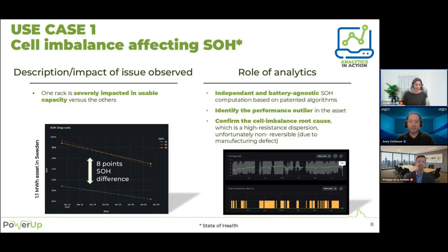What you see on the graph on the left are three lines, each representing one battery rack of the system. As you can see, one of them, the green one, is fully misaligned with the others. That means two racks have a relatively high state of health, while the third is 8% below the others, showing a clear underperformance with this rack.